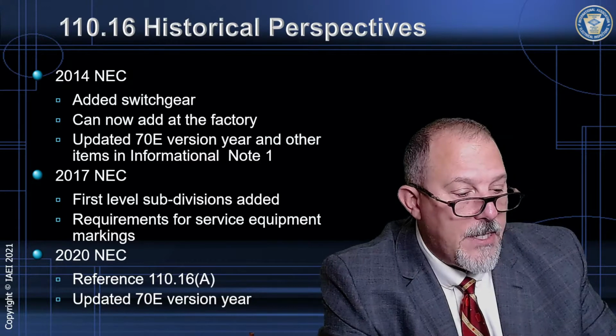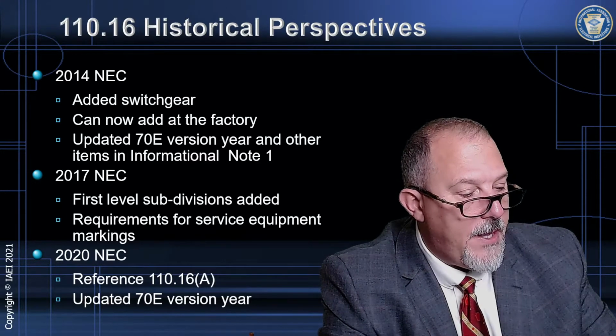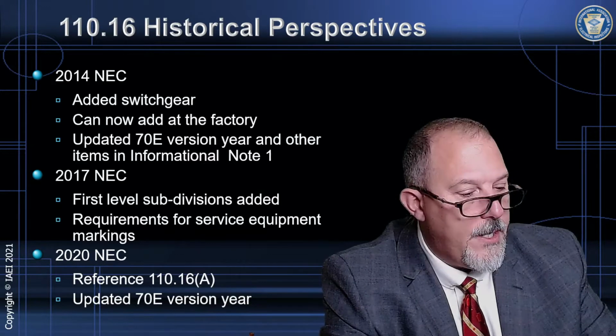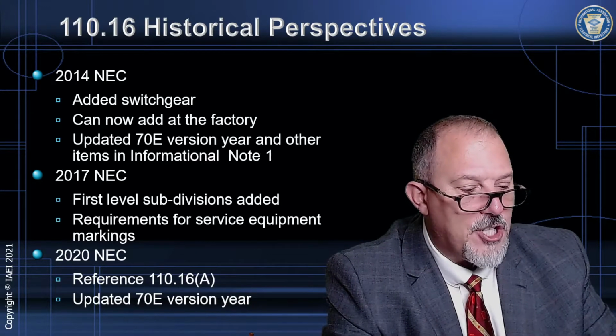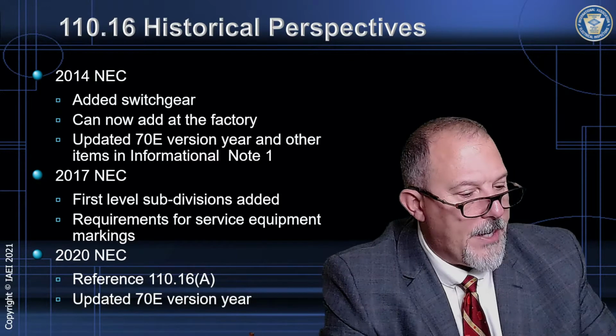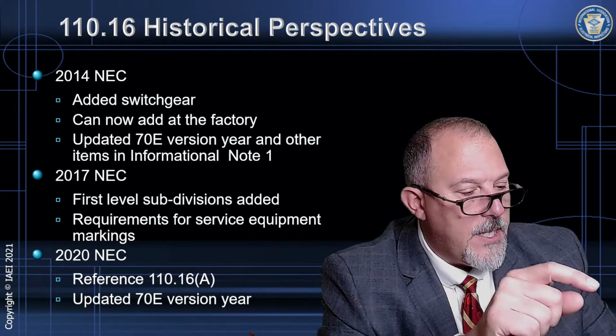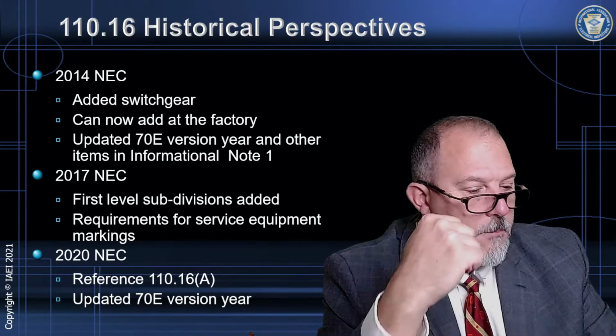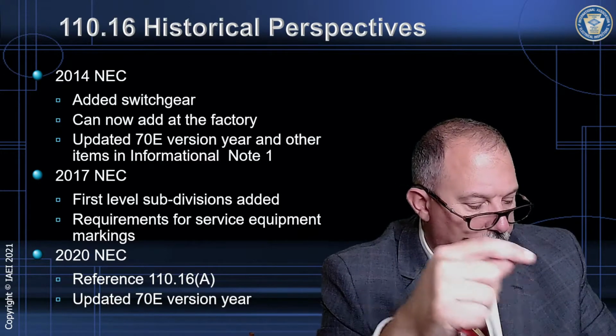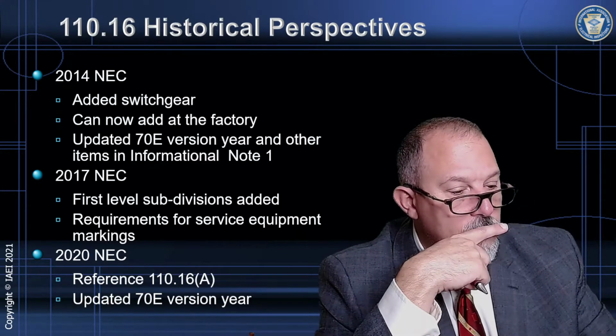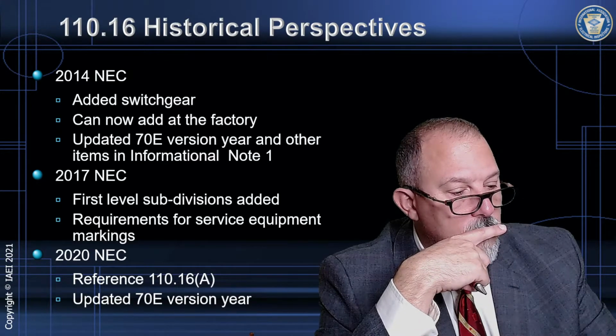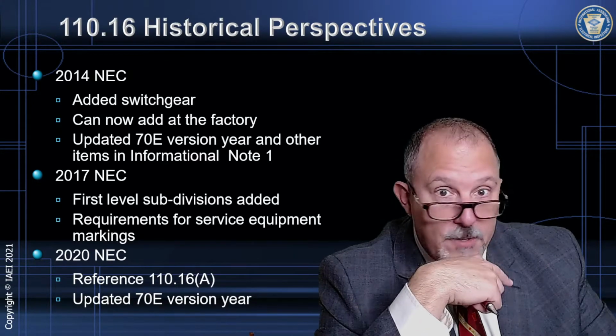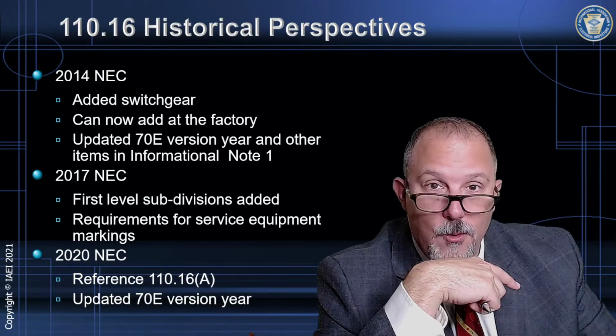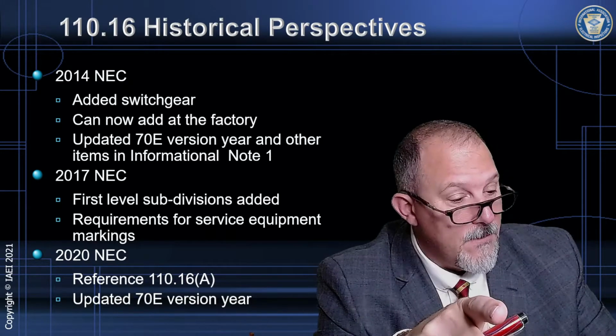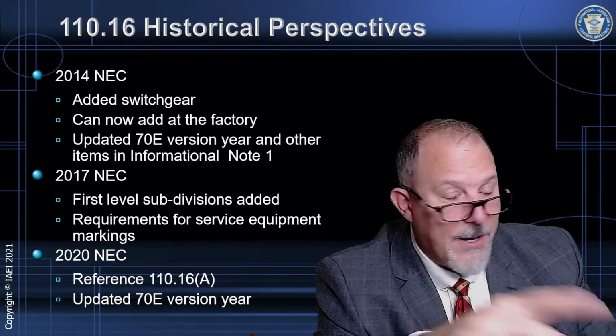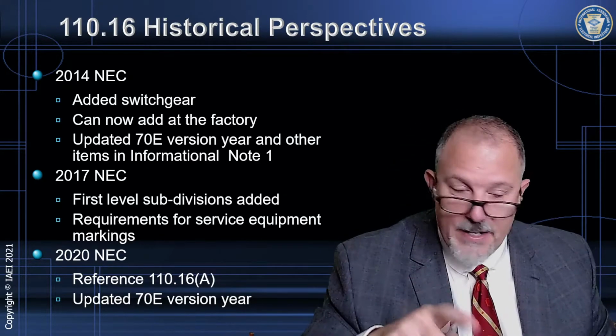And we updated the version of 70E, and then some informational note number 1, guidance such as arc flash labeling. So they just added some clarity there. So we said that these arc flash hazard warnings have to meet the requirements in 110.21(B), which is field applied hazard markings. But really, they should have said just 110.21. Think about it. And I don't know if we fix that later, but we're going to find out.